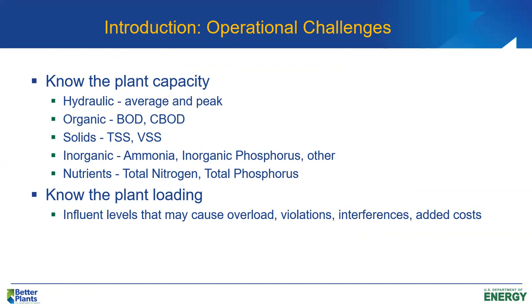One of the things we've got to do is know our plant. We've got to know our hydraulic loadings — what is the average daily flow rate the plant is designed for, the peak daily flow rate, the organic loading in pounds per day of BOD, the suspended solids loading design capacity, and how much ammonia nitrogen the plant is designed for. We also need to know the nutrient loading: how much nitrogen and phosphorus is coming in in the raw wastewater in pounds per day. We normally deal in concentrations in milligrams per liter, but it's more important to us as a design engineer and operator to know those loadings in terms of mass — pounds per day.